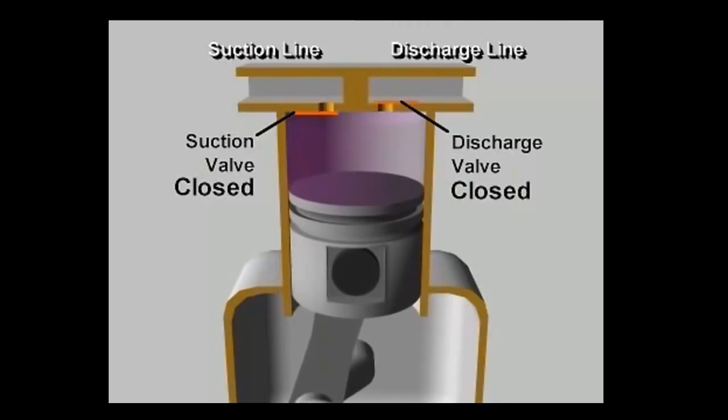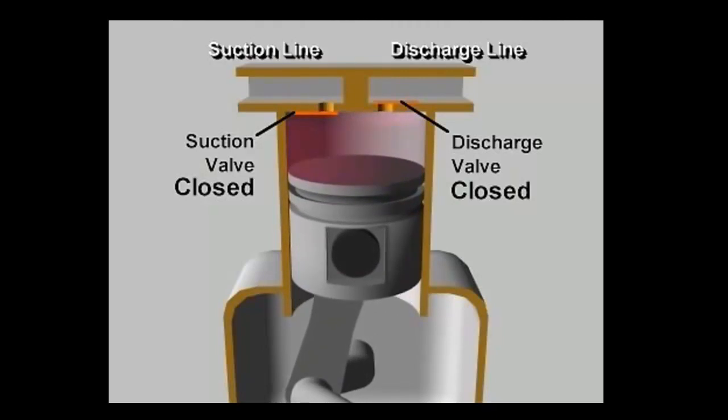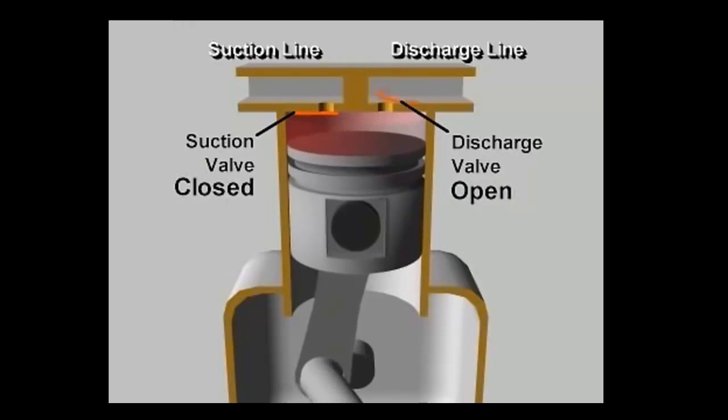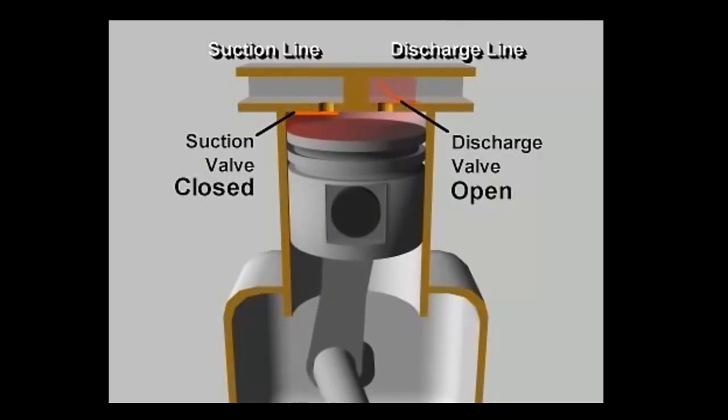As the piston moves up, it reduces the volume of the space in the cylinder, increasing the pressure of the vapor. When the pressure in the cylinder exceeds the high side pressure in the discharge line, the pressure difference pushes the discharge valve open, letting the compressed vapor flow out of the cylinder.